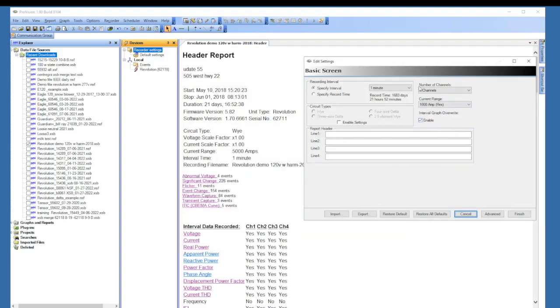So on the basic screen is where you can set up your interval. You can select how many channels you have, and you select your current range. Your interval, again, you can adjust, but that will also adjust your record time. You can see the record time; this recorder does have a 1 gigabyte memory. You can go all the way down to 1 cycle, so you get an average, but you also notice that there's only 1 day of recording. So the interval impacts the amount of record time that you have. But in most instances, 1 minute is acceptable.